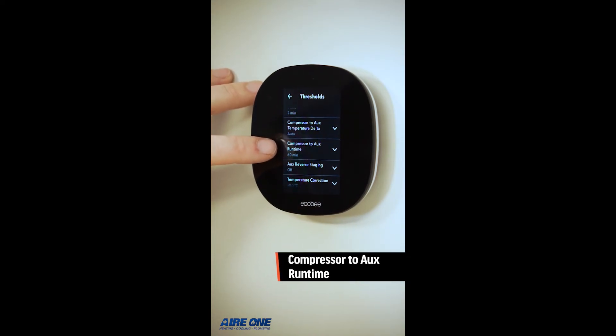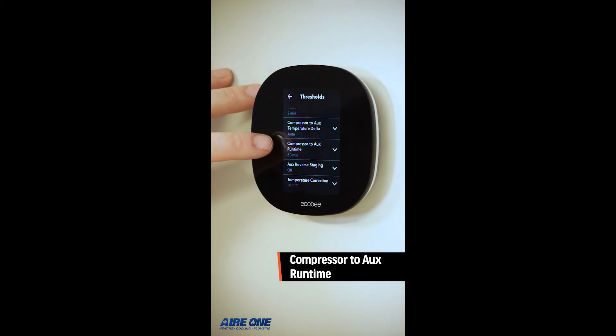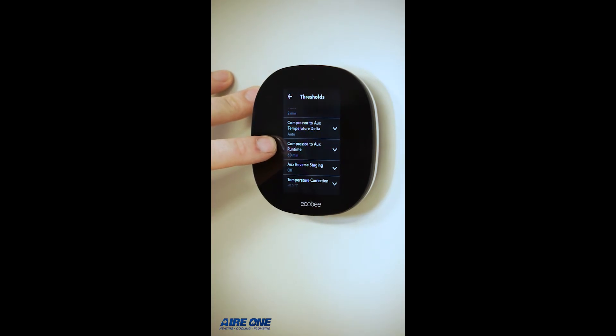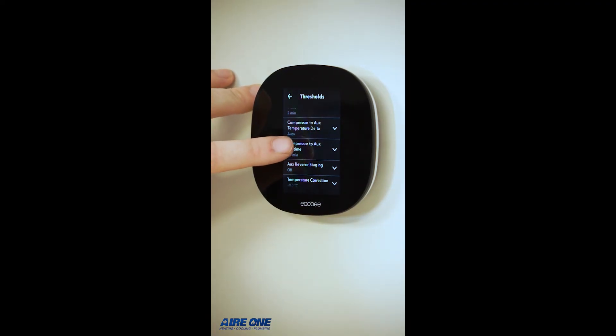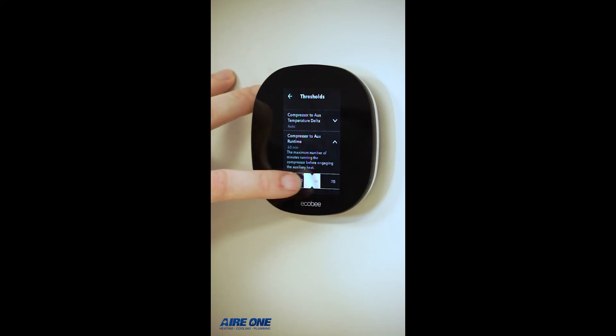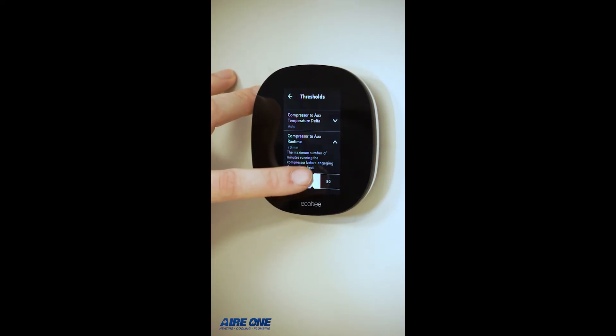Then scroll down to Compressor to Aux Run Time. It's currently set to 60 minutes, meaning the heat pump will run for 60 minutes, and if the thermostat is still calling for heat after 60 minutes, the auxiliary heat will kick on. You can click on it and slide left or right to increase or decrease the time.